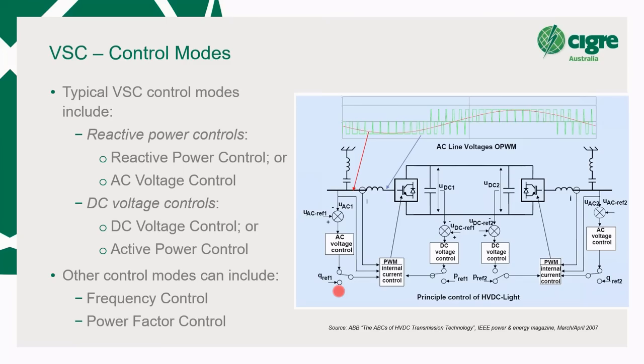But the AC voltage reference, if you're in AC voltage control, you just work out in the normal manner in which a system operator will determine what voltage they want to operate at. You just enter that value into your controls, and the converter will generate and absorb reactive power within the limits, within the ratings of the converter.